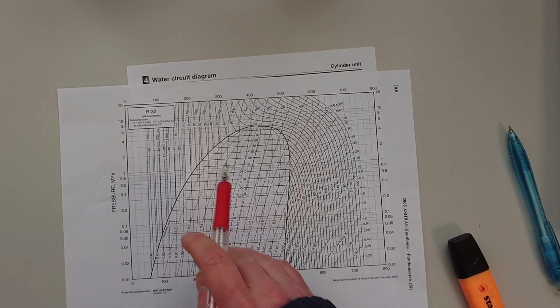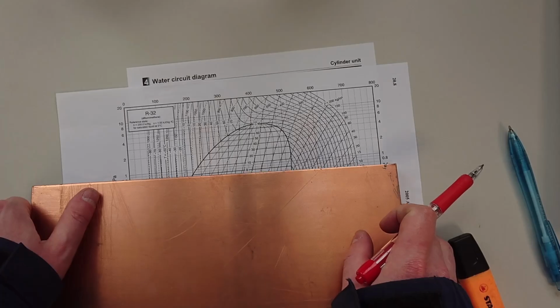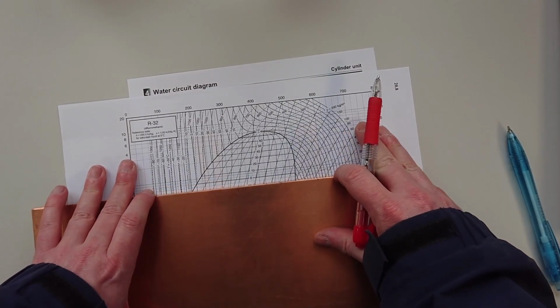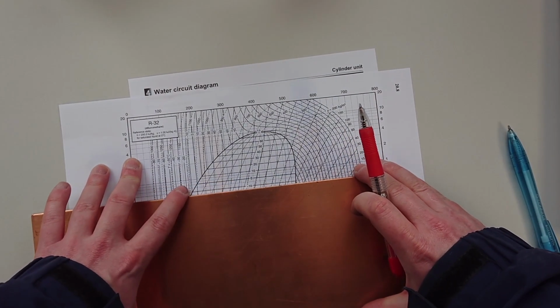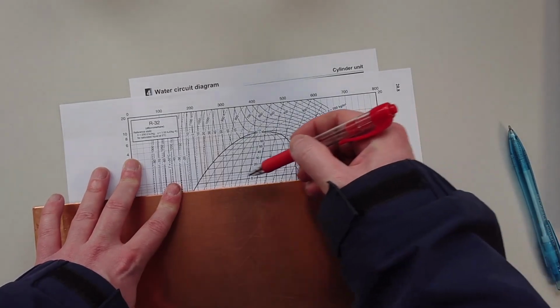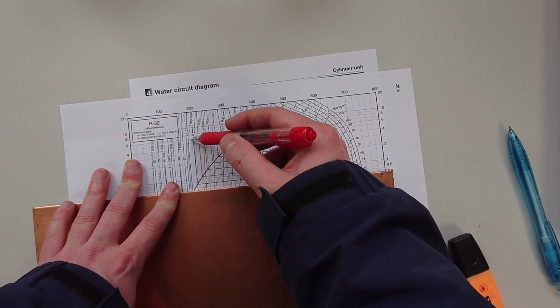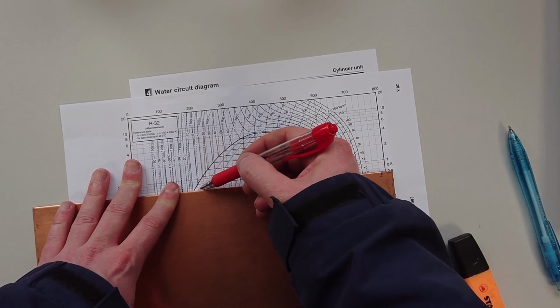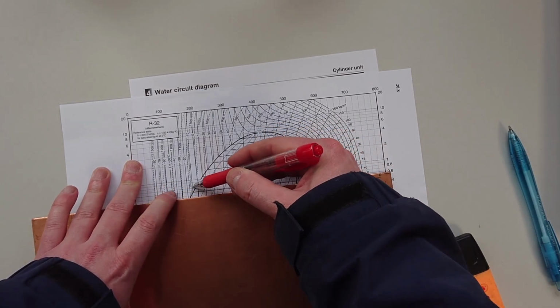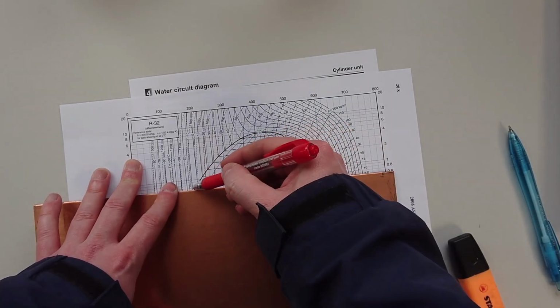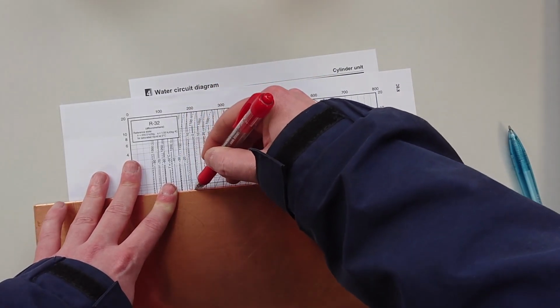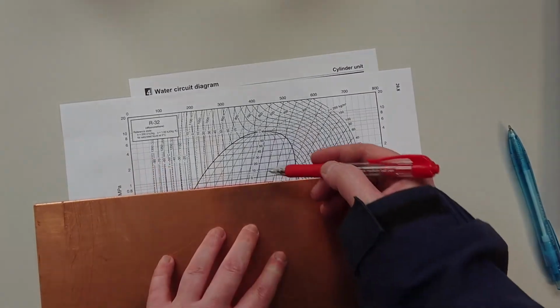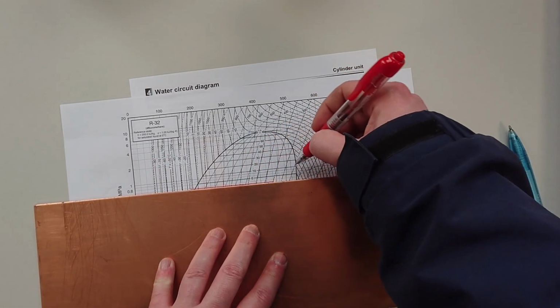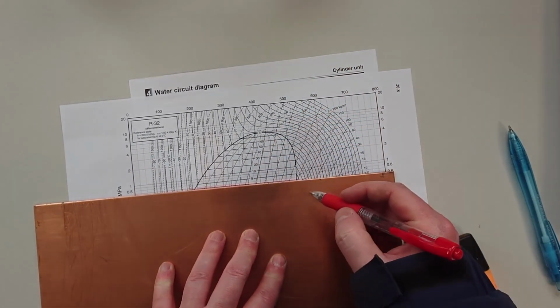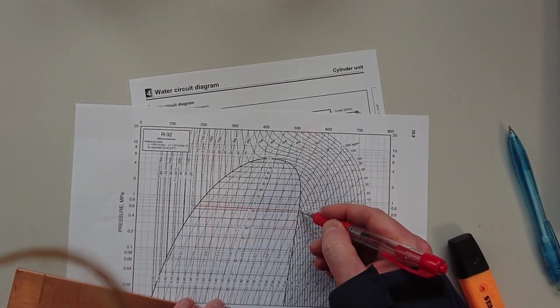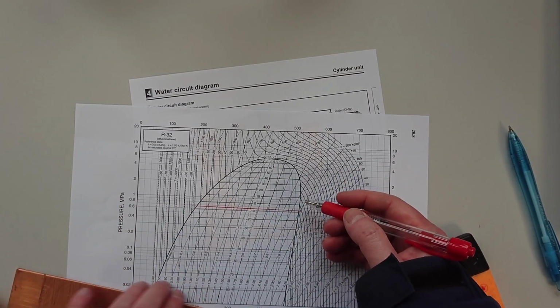that you can compress gas easily and you can't compress liquid easily. But if we start here, for instance, and we draw a line on our evaporating temperature, which is going to be whatever the temperature is below 0, and we'll just say it's somewhere around -10 or something. We're going to go from -10 and we're going to go straight through this evaporating part, and we're now evaporating moisture or liquid in the coil that's outside, and we're going to go to 0 because that's what your outside temperature is, and we're assuming there's nothing fancy like no heat exchangers, which there will be.